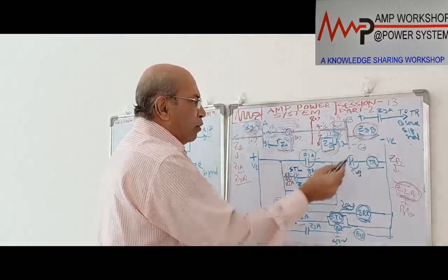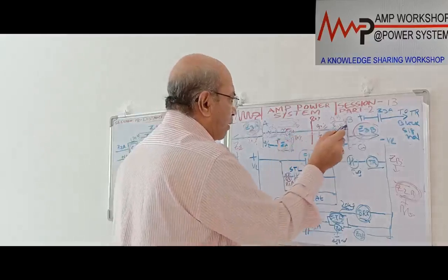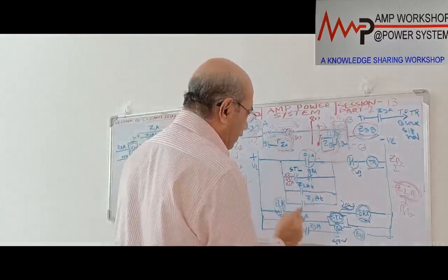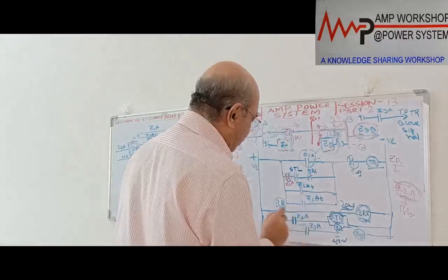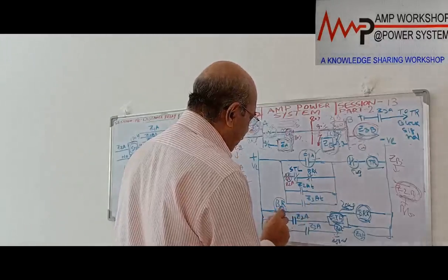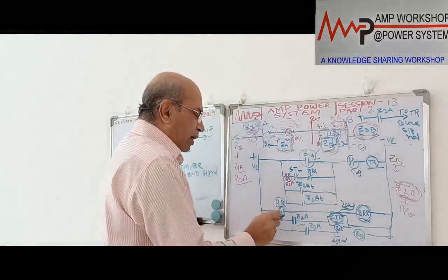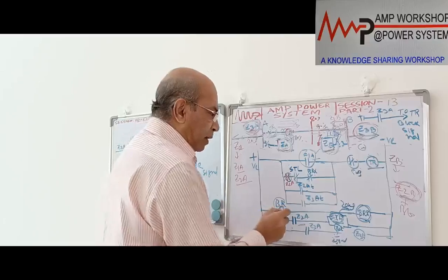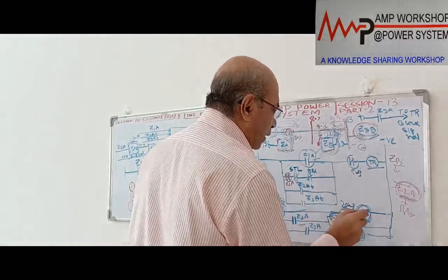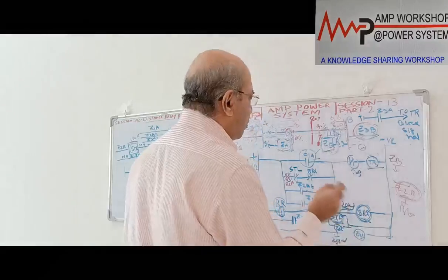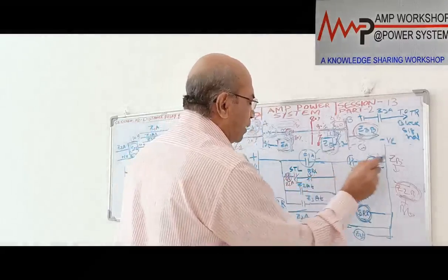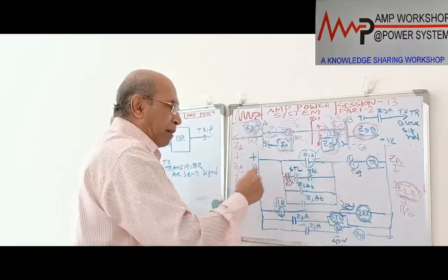Within the time, no signal is received from the other end. From this end, no signal has come over here. That is a BRX, a received signal. BR is a blocking signal relay, with contact NO. That means blocking signal relay not energized, meaning no blocking signal has come. When it has not come, BRX is also not energized. So the BRX NC contact gives the tripping, and this is a primary expedite tripping.